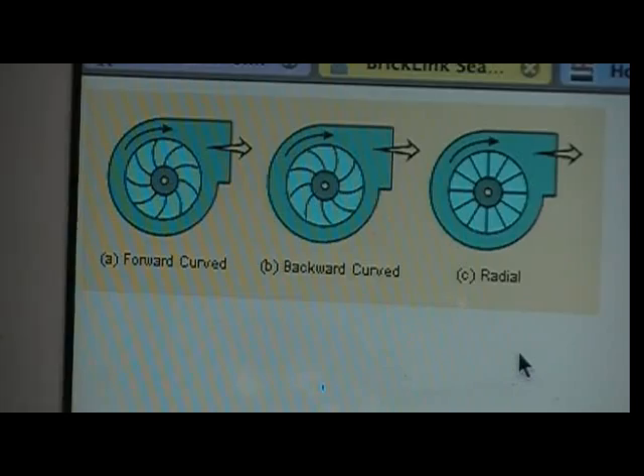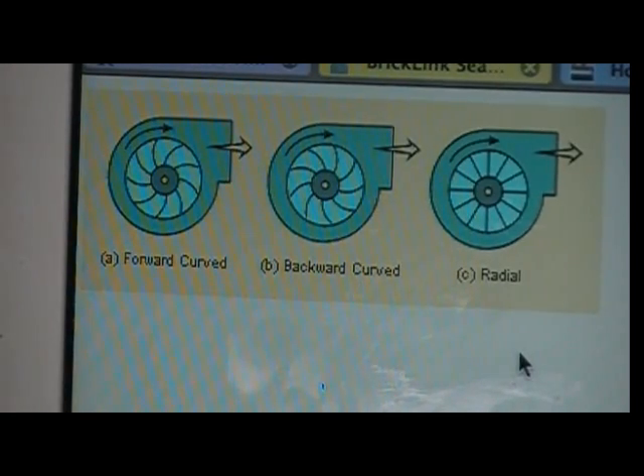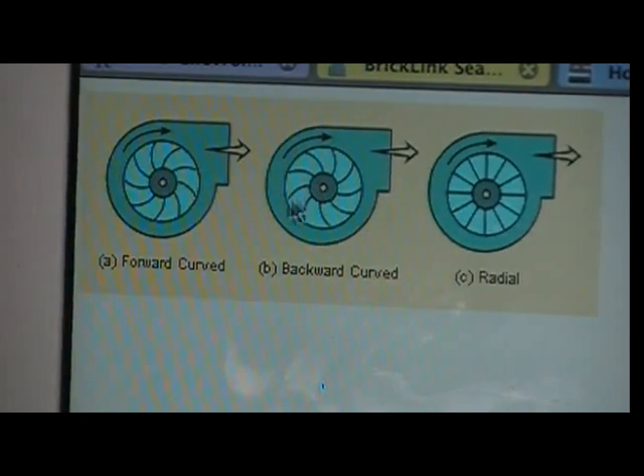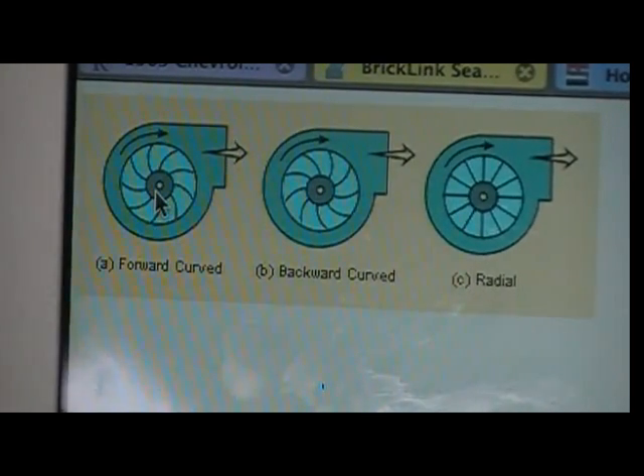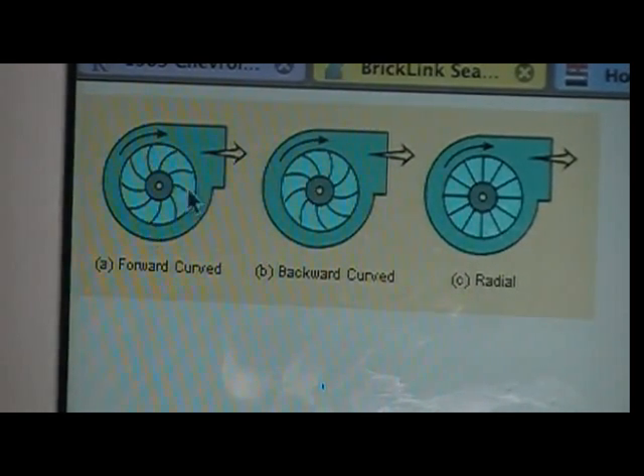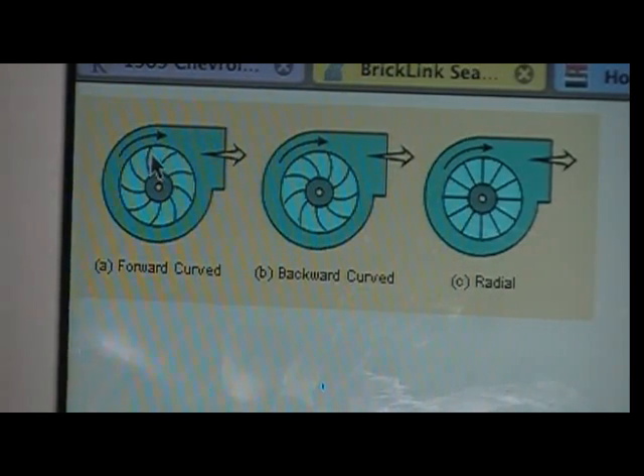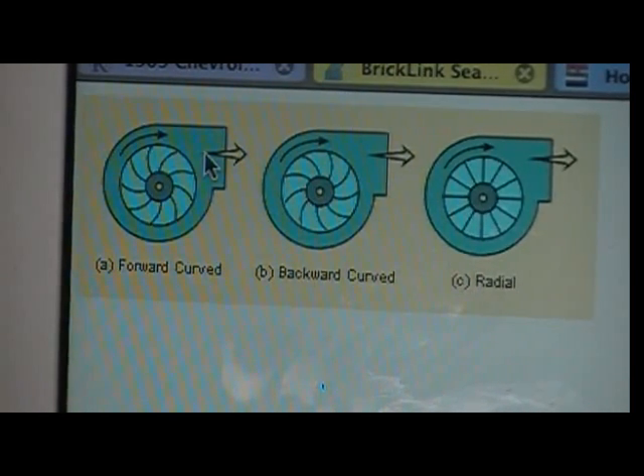There's three different types of fan blades on the fan wheel. There's the forward curved, which is used for relatively low pressure, high volume applications, like hot air dispersion.